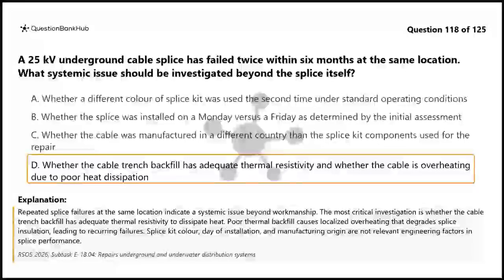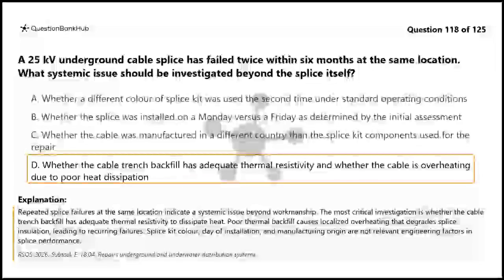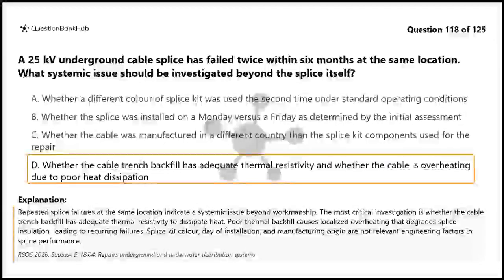The correct answer is D. Repeated splice failures at the same location indicate a systemic issue beyond workmanship. The most critical investigation is whether the cable trench backfill has adequate thermal resistivity to dissipate heat. Poor thermal backfill causes localized overheating that degrades splice insulation, leading to recurring failures. Splice kit color, day of installation, and manufacturing origin are not relevant engineering factors in splice performance.